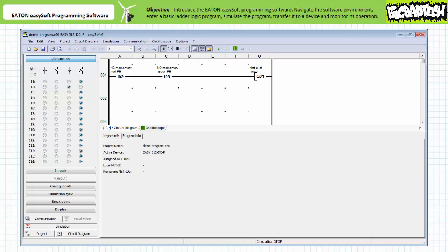Here we've instantiated the simulated field input device attached to input I2 as a normally closed maintain contact button, and the simulated field input device attached to input I3 as a normally open maintain contact button. Recall that the electromechanical nature of a field input device has absolutely nothing to do with how that input is logically instantiated in the program. Recall that a make instruction disallows logical continuity where that input experiences logical zero and allows logical continuity where that input experiences logical one. As dictated by the normally closed nature of the simulated field input device attached to input I2, input I2 would experience a logical one and the make instruction would allow logical continuity when the simulated field input device is in its deactivated normally closed state. When placed in its activated open state, it would receive a logical zero and disallow logical continuity. In contrast, as dictated by the normally open nature of the simulated field input device attached to input I3, input I3 would experience a logical zero and disallow logical continuity when the simulated field input device is in its deactivated normally open state. When placed in its activated closed state, it would receive a logical one and allow logical continuity.